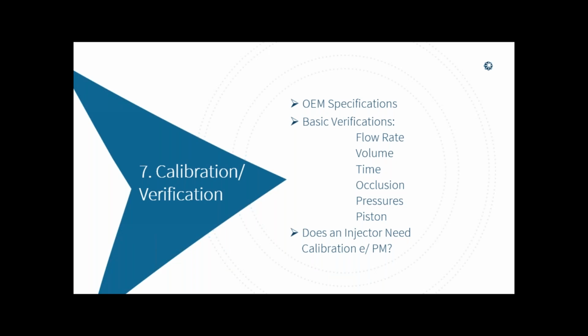Calibration verification. You complete the PM to meet OEM specifications. Basic verifications are flow rate. Oh wait, who's worked on infusion pumps before? Okay, this is going to sound very familiar to you. Flow rate, right? Volume, time, occlusion, pressures, and maintaining the piston calibration. Does an injector need calibration during a PM?